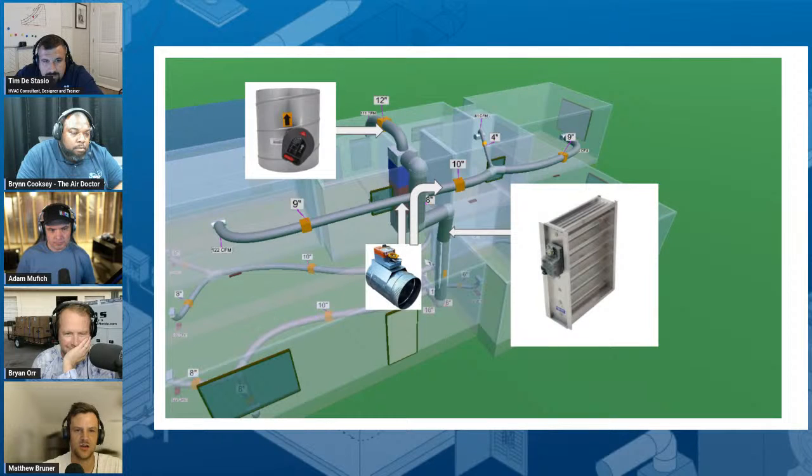It needed to be zoned. What I did with the airflow is, I didn't want to put 2 units in the house because they were on a budget. And I had to redo all the ductwork under the house because it had been crawled over and smashed and broken and was full of water because they had a crawl space flood issue.